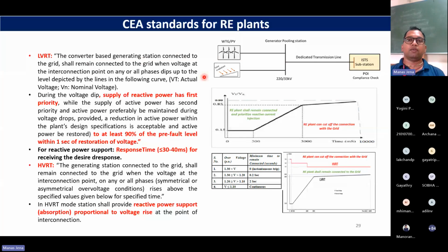So you have an inverter, the pooling station, and this is the ISTS substation. This is the point of interconnection, where the compliance will be checked, and this side will be your grid. If any fault happens in the grid and a low voltage scenario is created, you should not isolate yourself randomly. CEA has come up with this type of curve.